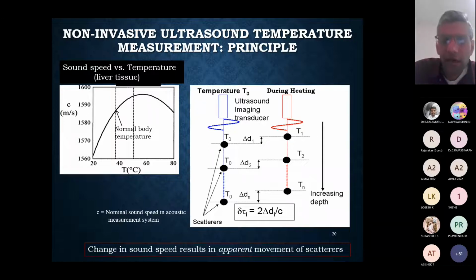right? Because the measurement is purely done based on the time it takes to go through the body and come back. So based on the change in the speed of sound, you're going to have a change in what we call the travel time, the time it takes for the echo to get to the tissue and back. And based on that, any image that you render is going to show as though these scatterers have changed their position. Although physically they haven't changed position, it's purely due to the change of speed of sound, and that's the reason we call it apparent change in the position of the scatterers.